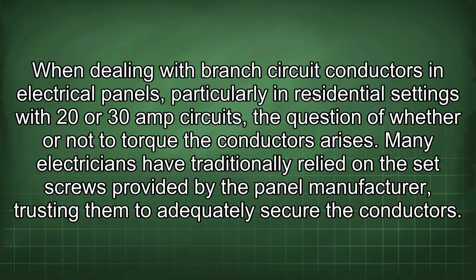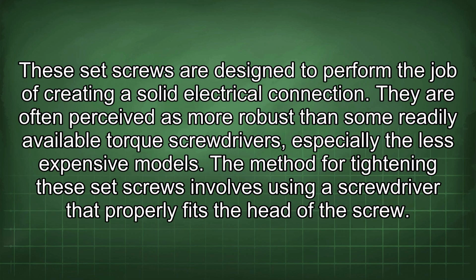When dealing with branch circuit conductors in electrical panels, particularly in residential settings with 20 or 30 amp circuits, the question of whether or not to torque the conductors arises. Many electricians have traditionally relied on the set screws provided by the panel manufacturer, trusting them to adequately secure the conductors. These set screws are designed to perform the job of creating a solid electrical connection. They are often perceived as more robust than some readily available torque screwdrivers, especially the less expensive models.